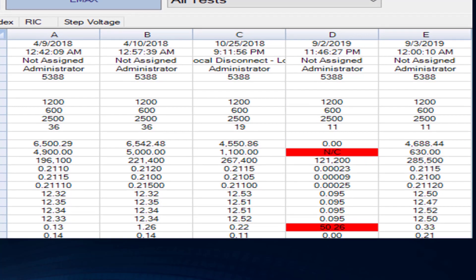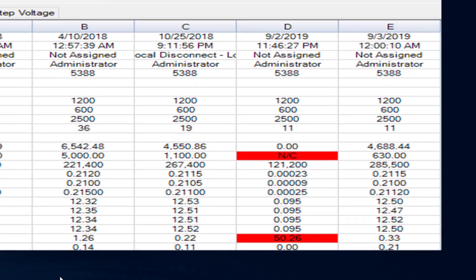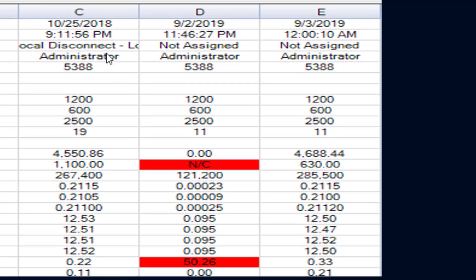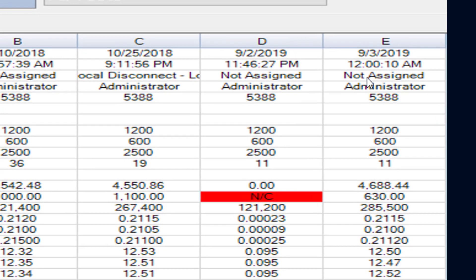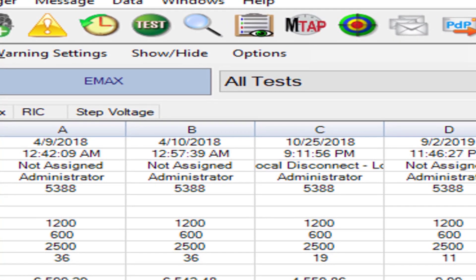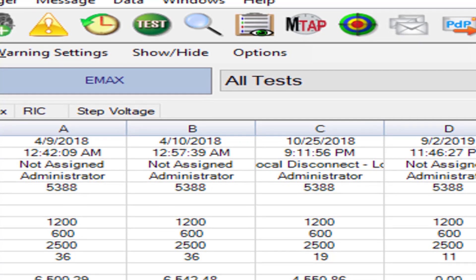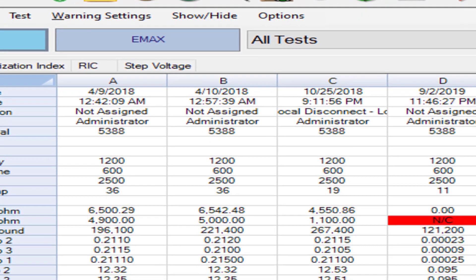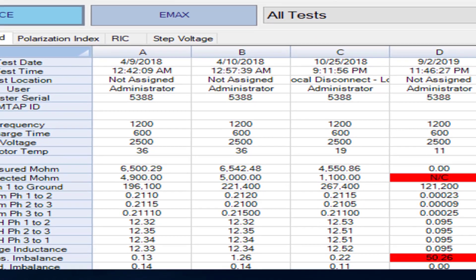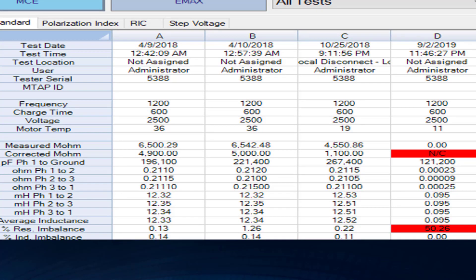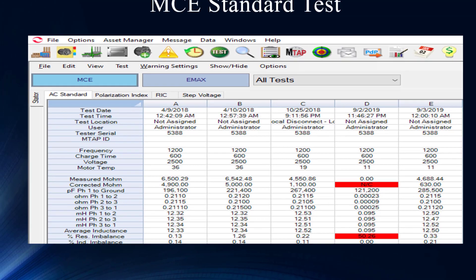One of the things that stands out is the alarming levels — it won't take long for an analyst to look at that and say, hey, this data obviously was from a different motor, a different test location. They should really clear that out to make sure it's not creating a false alarm. Test location is really important — right now looking at this, it doesn't tell me where that odd test location was. If we knew that was tested at the switchgear with just the cables, we would understand that data. The one component on this graph from the standard test to analyze rotors is average inductance — one of the six methods of rotor defect assessment. It starts out about 12.3 millihenries and ends at 12.5 — not a huge difference, but it's another thing you can correlate to say it's indicating a change and it correlates with the spectrum, making you more confident in making a call.